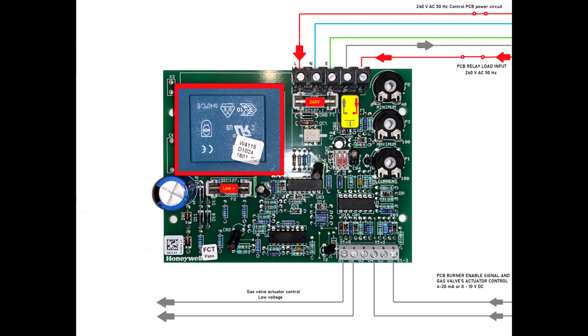Now when you close that circuit and you have power to that relay, still the signal will not continue its journey because that relay is not enabled. The printed circuit board will never enable that relay until the building management control or the programmable logic control or the thermostat provides 4 to 20 milliamps or 0 to 10 volts to these bottom right hand side wires. That's a signal which will demand heating, and you will see how this will work. So at this stage, this printed circuit board is enabled, and the signal that's supposed to activate a burner is on standby.